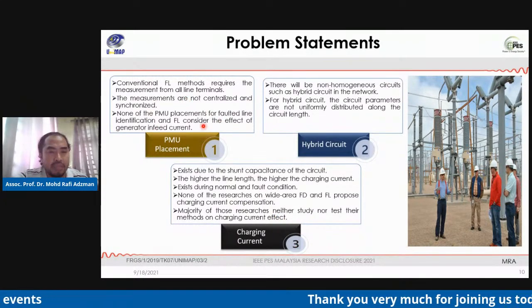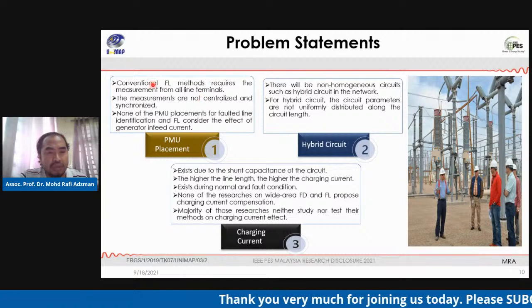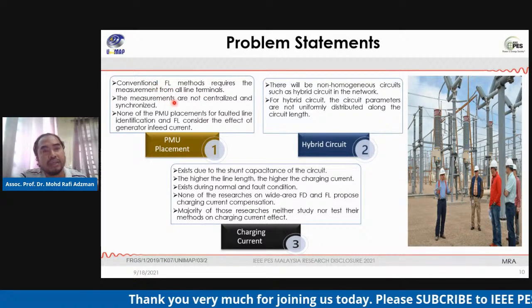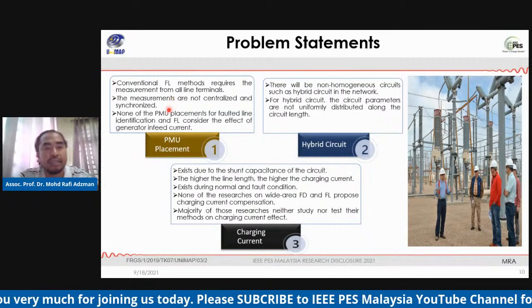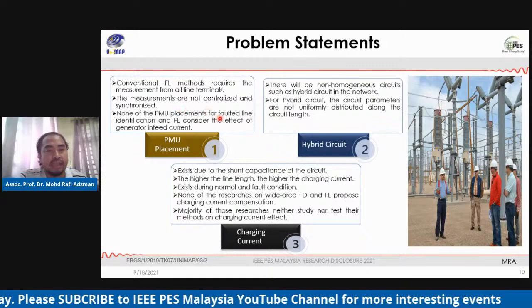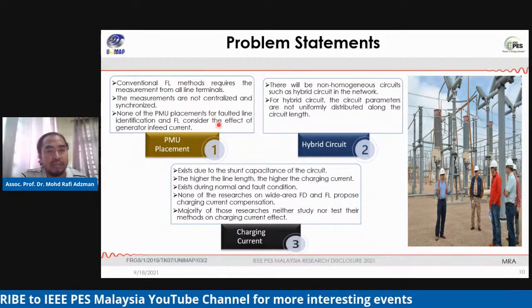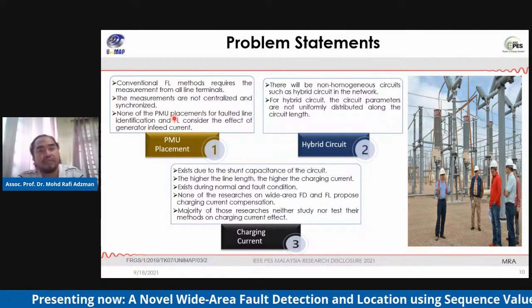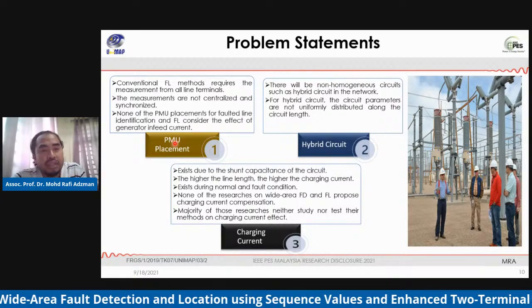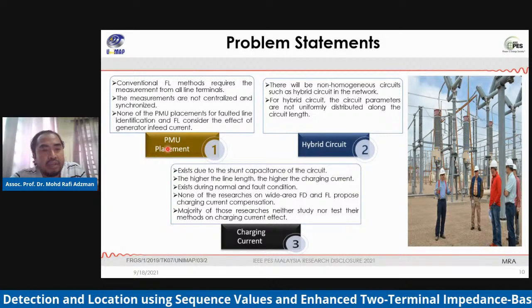Regarding the PMU placement, the conventional fault location methods require the measurement from all line terminals. And normally the measurements are not centralized and synchronized. Based on our findings, none of the PMU placements for faulted line identification and fault location were considered with the effect of the generator in-feed currents.